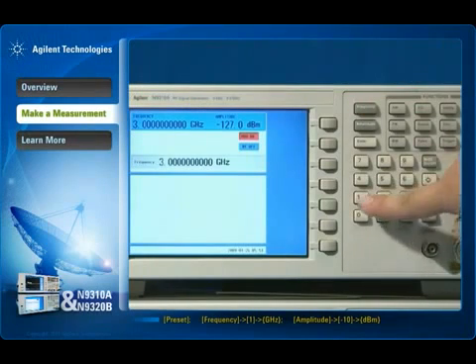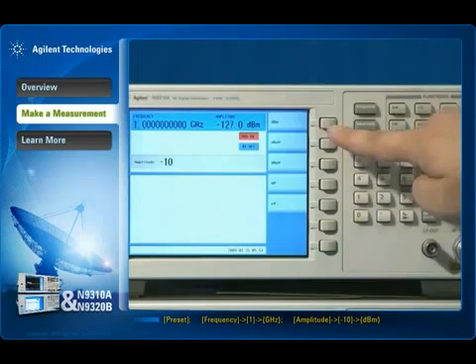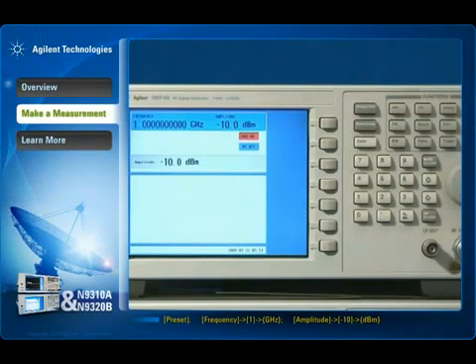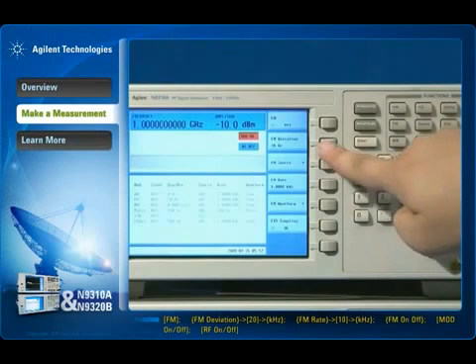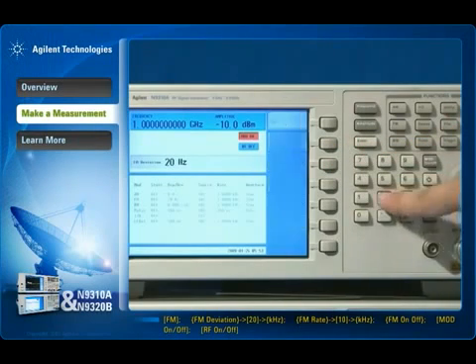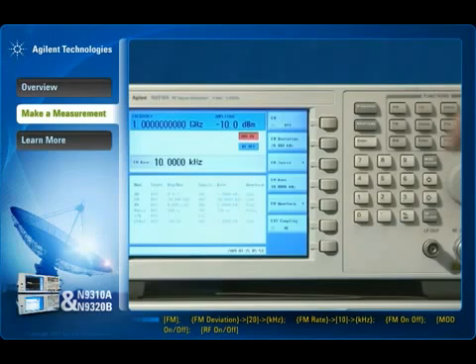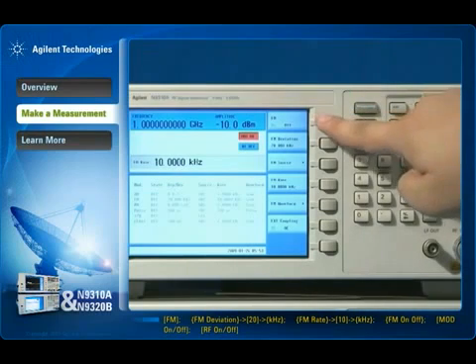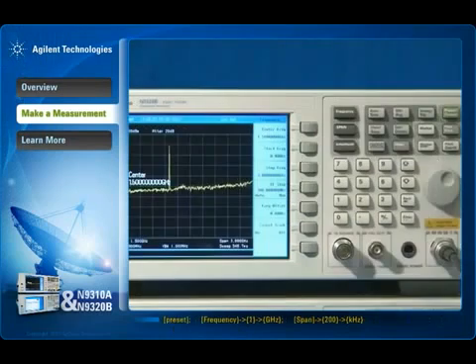First, select the carrier frequency and amplitude. Next, select the FM modulation parameters, which include the FM deviation and FM rate. Finally, activate the mod and RF output. Now the FM signal is being generated.